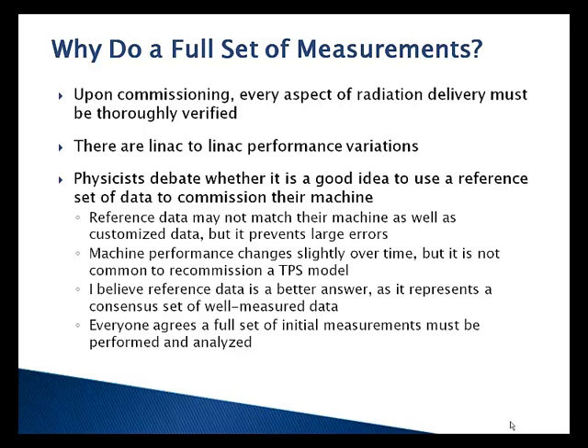Why did I do a full set of measurements in the first place? Upon commissioning, we always do a full set of measurements. There are, indeed, Linac to Linac performance variations, maybe on the order of 1% or 2%. And physicists internally debate whether we should do a full set of measurements every time we get a Linac or if we should use reference data. The reference data is not going to match exactly our particular Linac. But on the other hand, if our particular Linac changes over time, we're not going to recommission the planning system either. We're just going to try to put it back where it was.